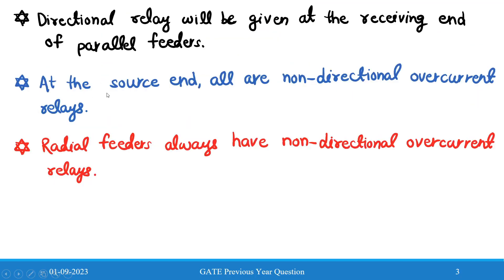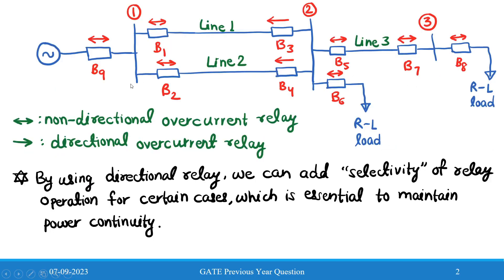The second point is that at the source end, all relays are non-directional overcurrent relays. We have the generator, and the relays beside the generator on the source side are all non-directional overcurrent relays — therefore R1, R2, and R9 will be non-directional overcurrent relays.